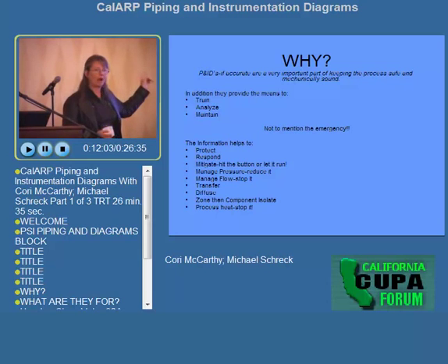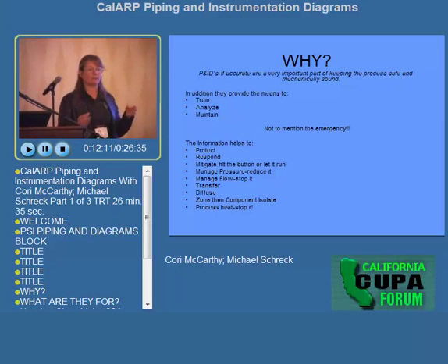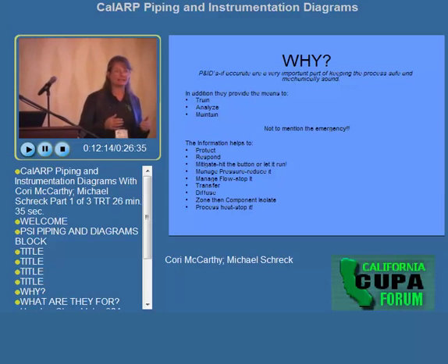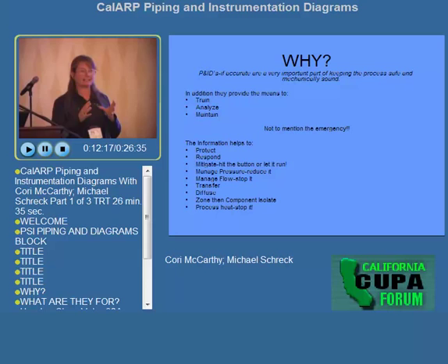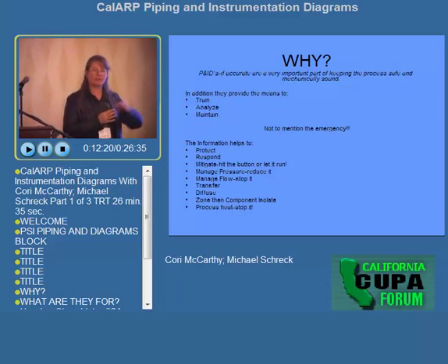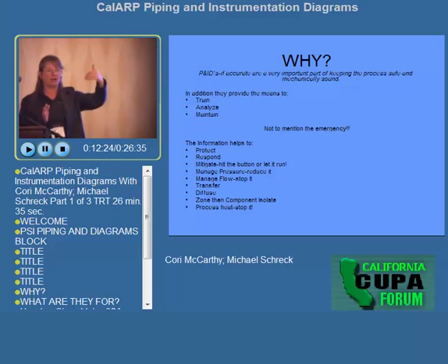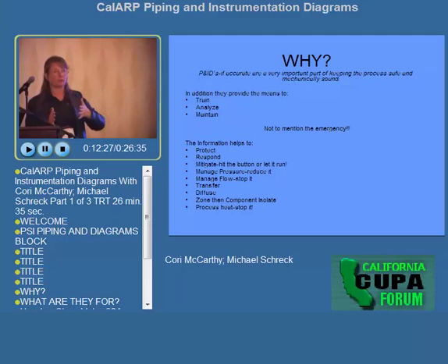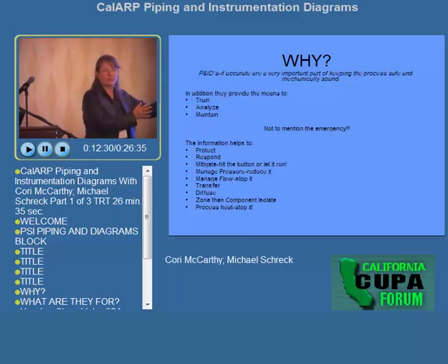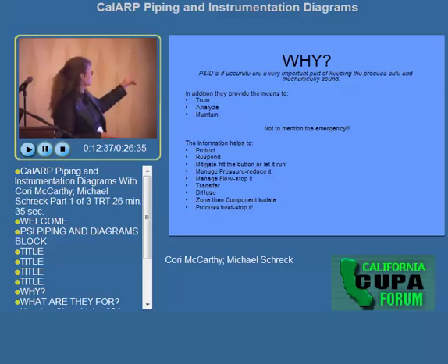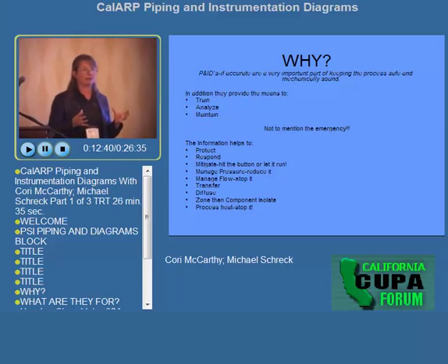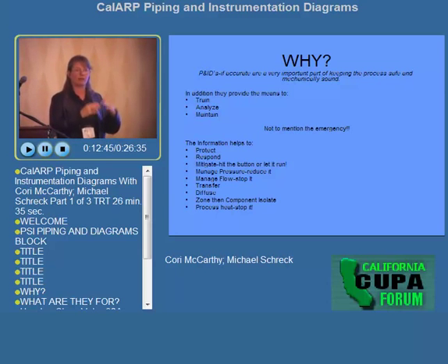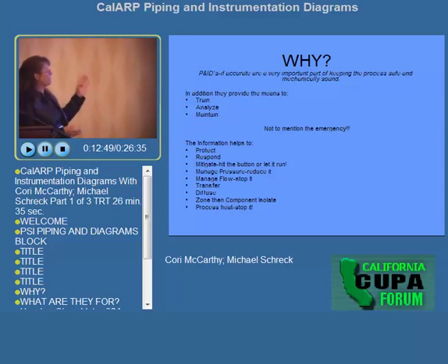We need to know how we're going to mitigate — are we going to hit the button and shut it down, or let the system run because that's a better choice? In many cases, depending upon where the leak is in the system, it's better to keep pumping so the ammonia goes back to the high-pressure receiver and is not allowed to backflow into the hole. If you shut your compressors down, you're no longer bringing ammonia vapor back to the compressors and into the high-pressure receiver.